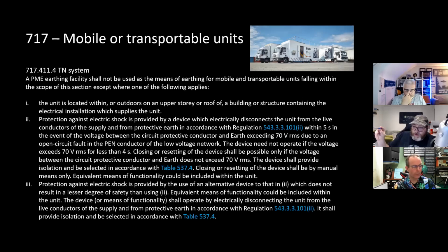So this is the temporary unit. Or we then have this regulation, which if we look at it, there's a mention there of 543.3.3, 101, 5 seconds, 70 volts for less than 4 seconds. It's the same thing. It's the same type of device, the same type of protection that we had back in 711, that we have in 722. So this device and this method of 70 volts for no more than 4 seconds, or it's got to turn off, is spreading.